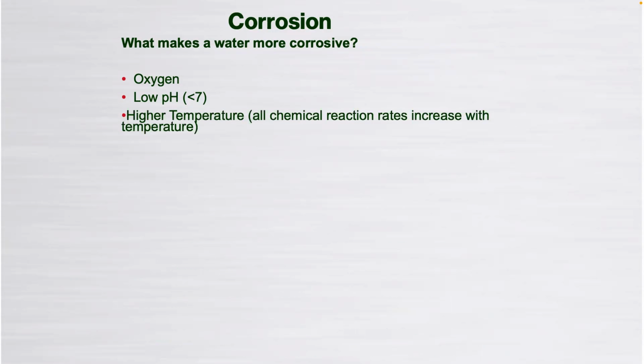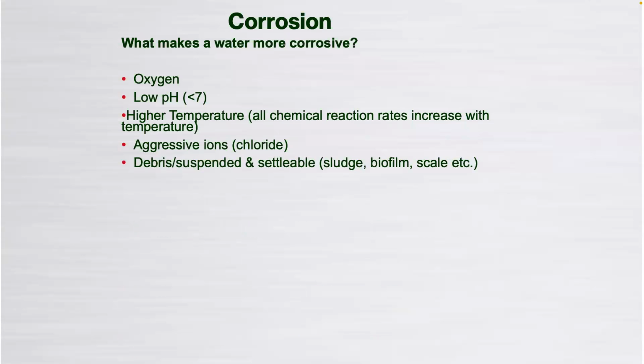Higher temperature, all chemical reactions do increase with temperature. So it's normally why you find a lot more of this black magnetite in a heating system versus a cooling chilled water system. You'll probably find you'll pull more biofilm and a lower level of iron from that system. Aggressive ions as well. So, chloride, for example, as I mentioned before, and that can even come from the mains water, depending on what sort of treatment regime the local authority is adding to the water, particularly if they've maybe had a bad count of bacteria.